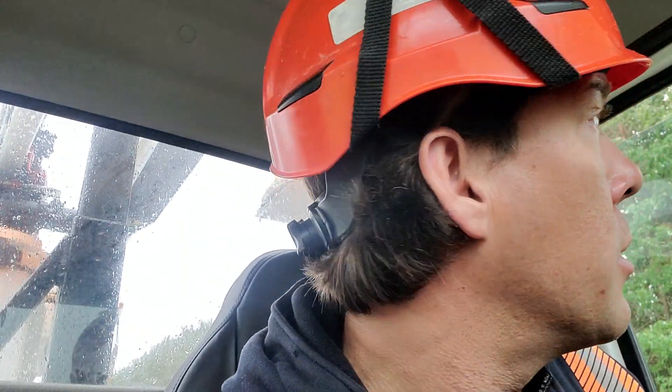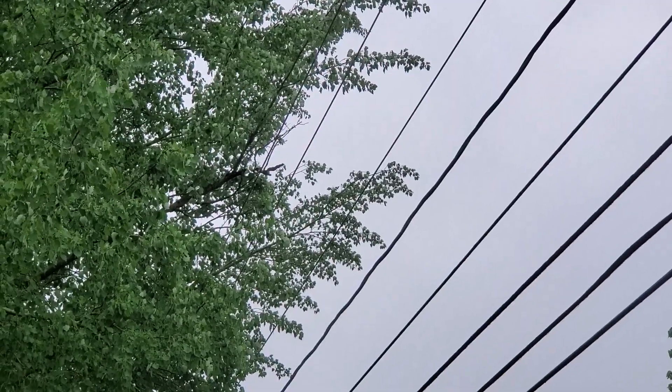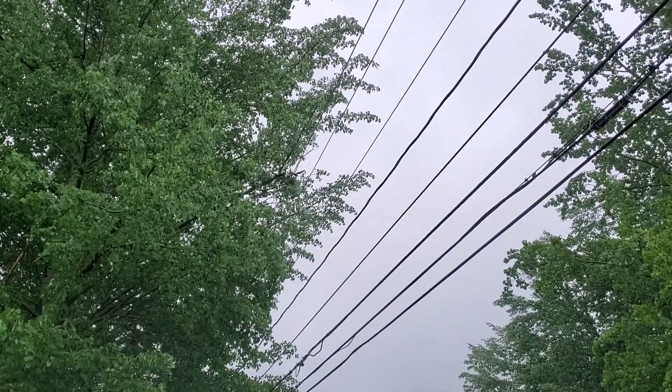That's good news — really good news. The report from the customer was that it was a pole on fire, but it's actually nothing more than a branch. You can see the burn marks on the branch on one phase. It is a three-phase recloser, so a fault on just one phase will take out all three — it may unnecessarily open the other two phases. That said, it does shut off all three phases, which is much safer, and for three-phase customers it's not good to run equipment off two out of three phases. So once we lose one phase and all three go out, it's much better for our industrial customers which there are a few on this line.